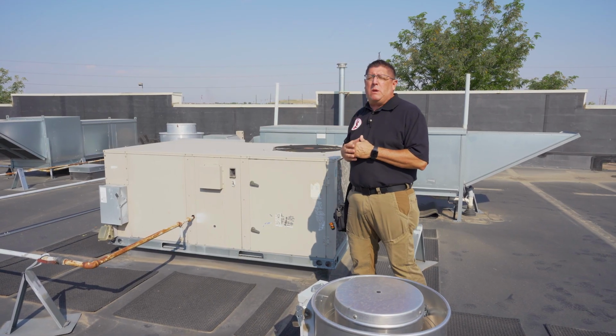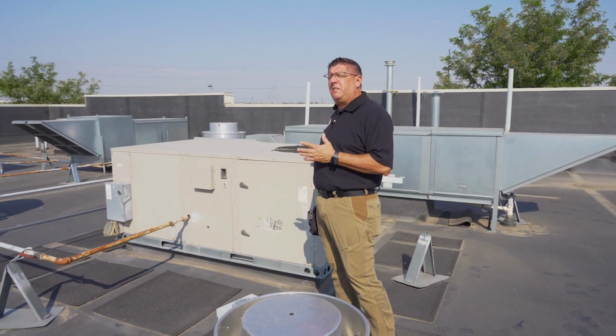When we're doing our heating inspection, it's important to look at all the air exits as well as the air intake for the unit. All exits of anything on the roof can't be within 10 foot of this piece of equipment.